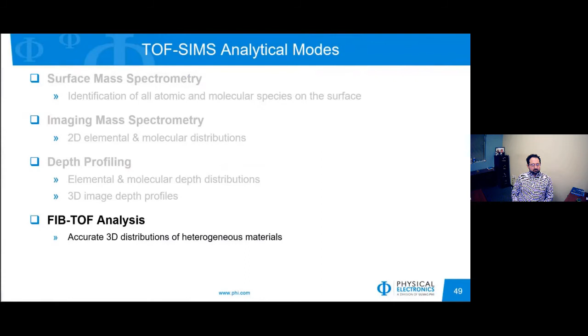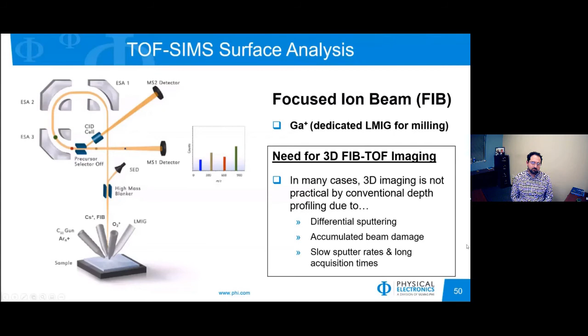So going into the last analytical mode of TOF-SIMS is FIB-TOF. And so you might be asking, well, I can just do a traditional depth profile going from the top down, but there are some issues associated with doing a top-down depth profile, several artifacts that can be caused just by doing a depth profile. So another ion beam choice you have is a focused ion beam used for milling. That's very similar to what's used in a FIB, a gallium liquid metal ion source here. And so why 3D FIB-TOF imaging? Because traditional depth profiles have differential sputtering, you can accumulate beam damage, as we saw with aerogel, and you can have slow sputter rates and long acquisition times. So these can all be mitigated by using a FIB-TOF analysis.